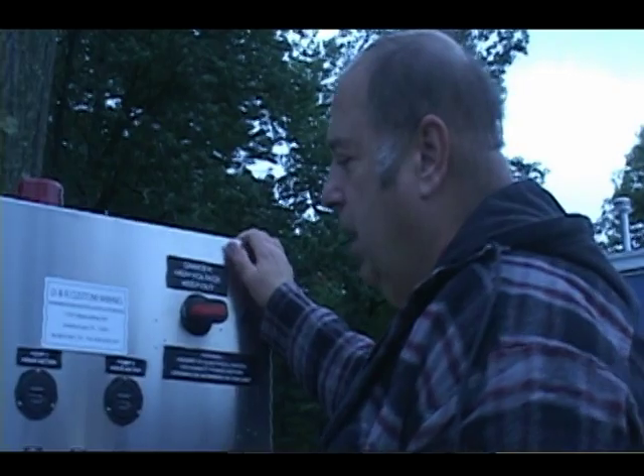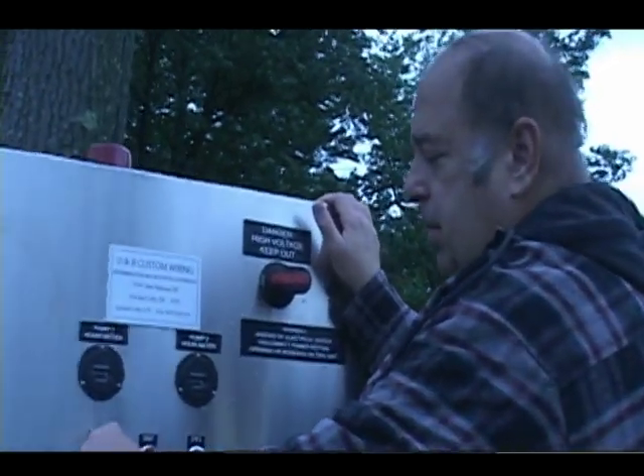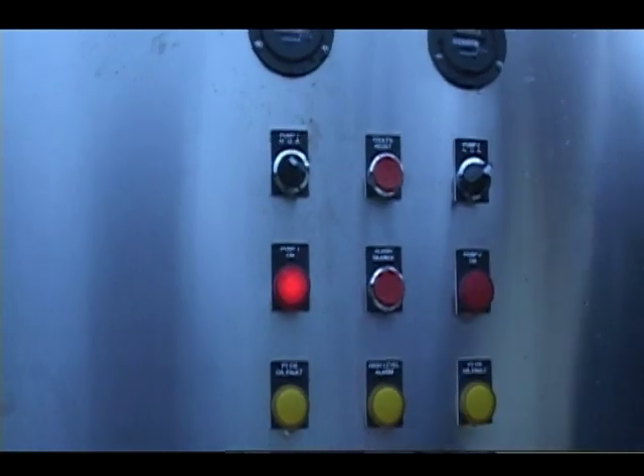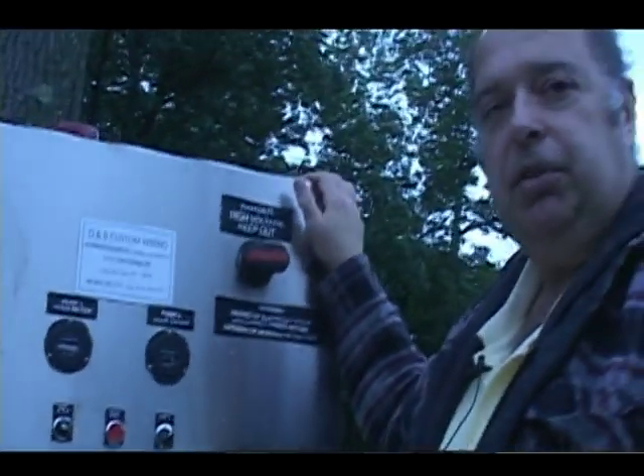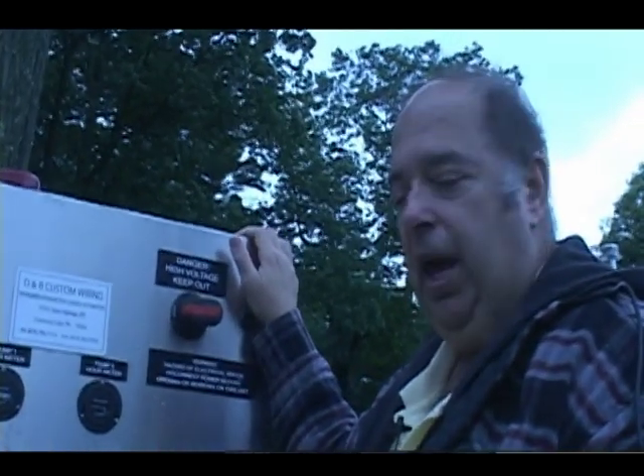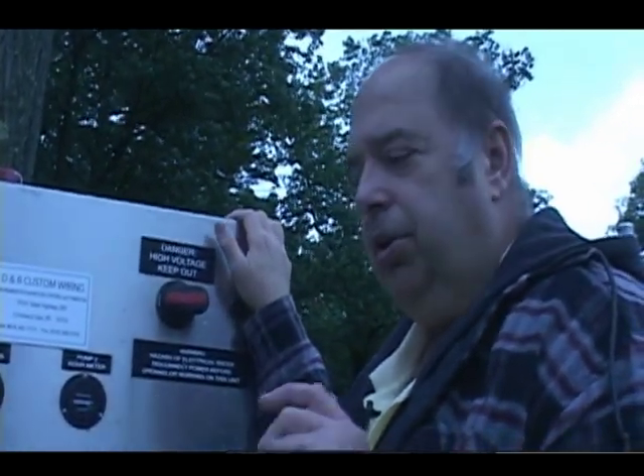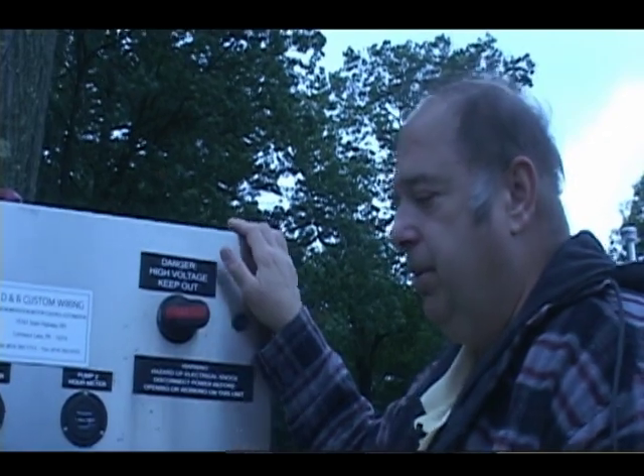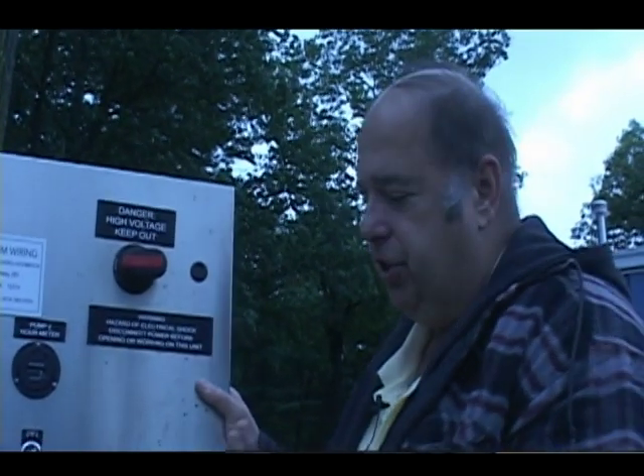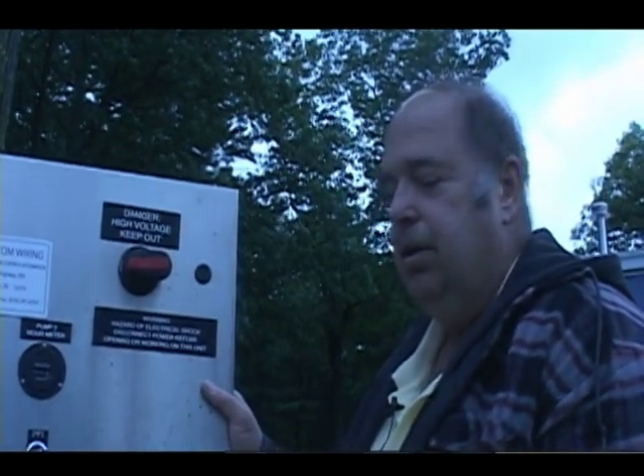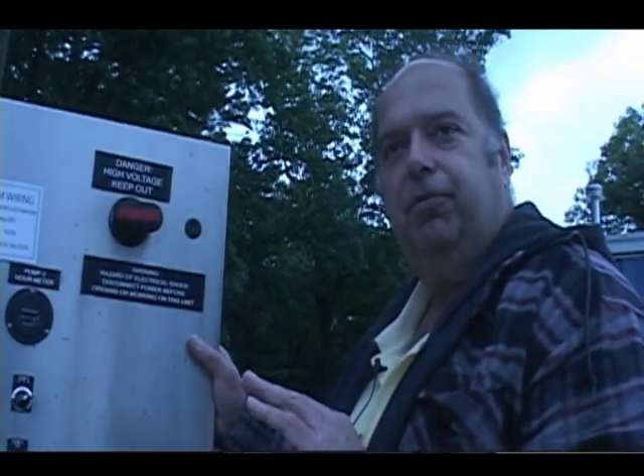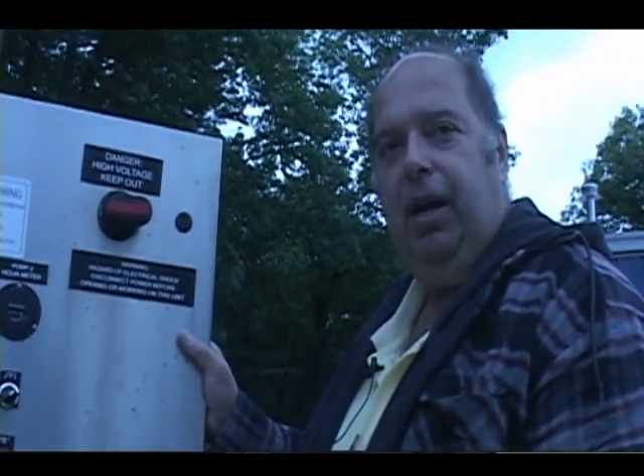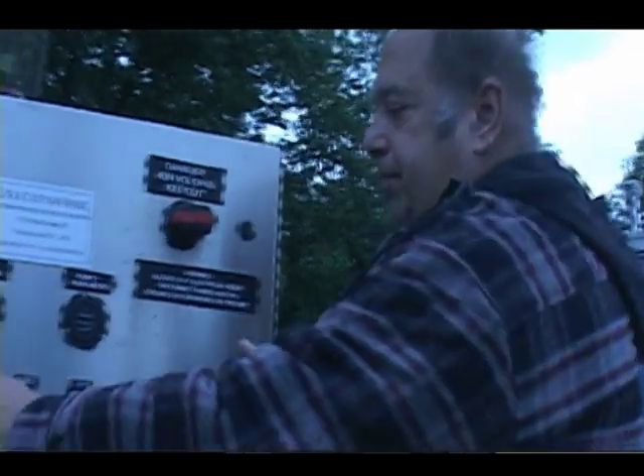Now, in the hand position, the pump will start. As you can see, it's on, and it will run until you shut it off. There is no off levels in the hand position. The faults will shut it off, such as an overload, a seal, or motor temp, okay? But that's the only shutoffs. Please do not run the pump for more than a couple minutes when it's dry. You will damage the pump.